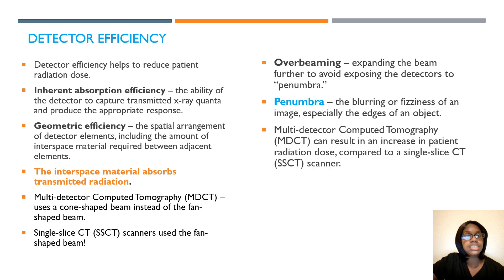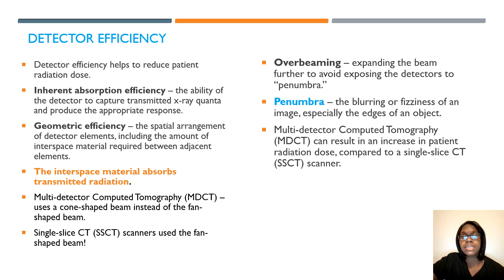For detector efficiency, this helps reduce patient radiation dose. Make sure you understand what overbeaming is, which expands the beam further to avoid exposing the detector to penumbra. Penumbra is the blurring or fuzziness of an image, especially along the edges of an object. Also keep in mind that multi-detector computed tomography can result in an increase in patient radiation dose compared to the single-slice CT scanner.